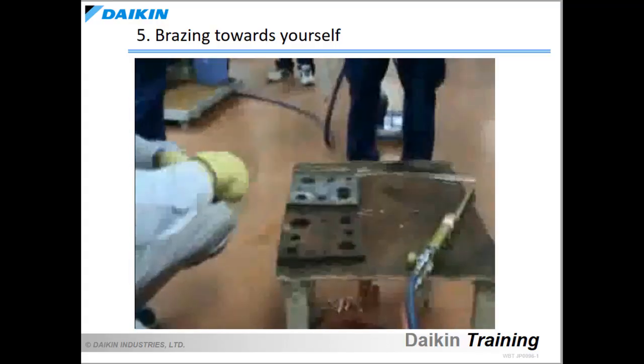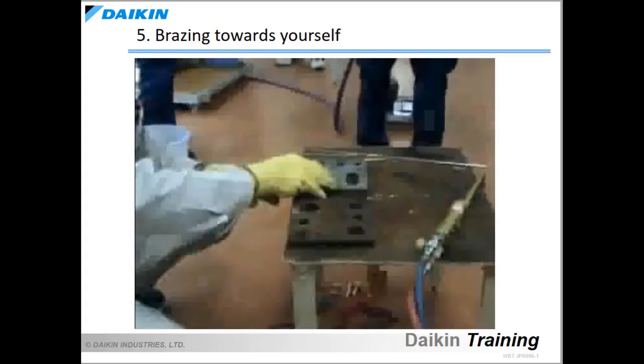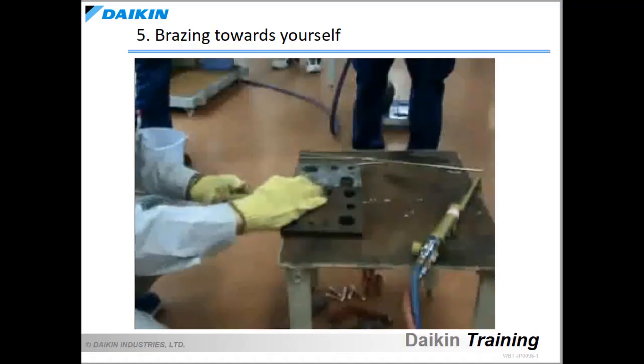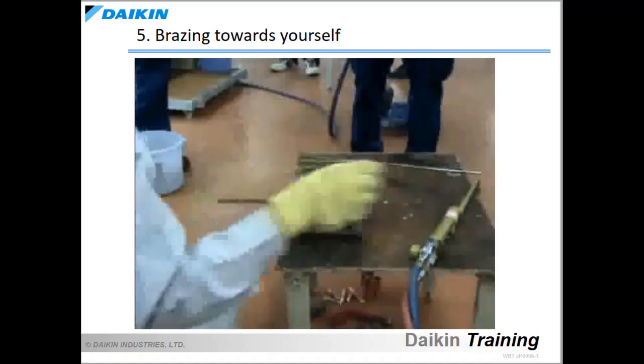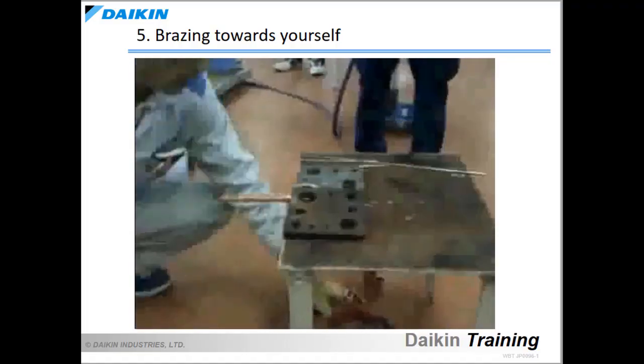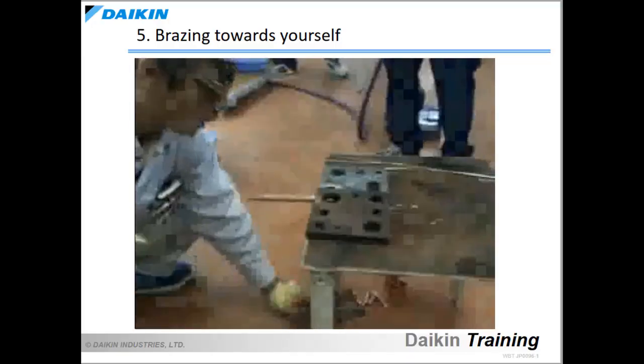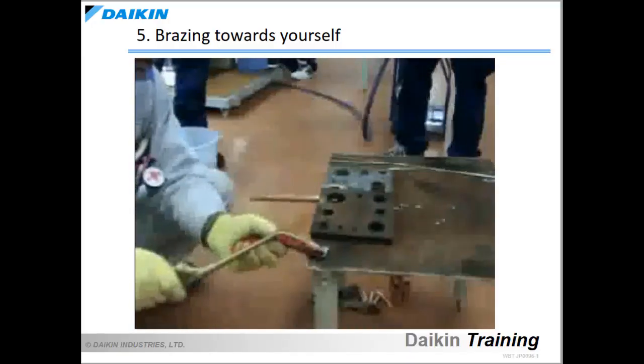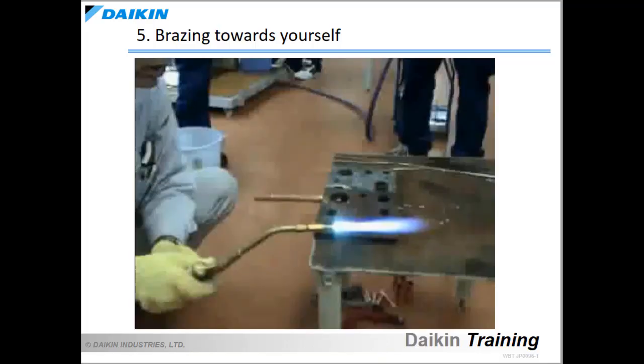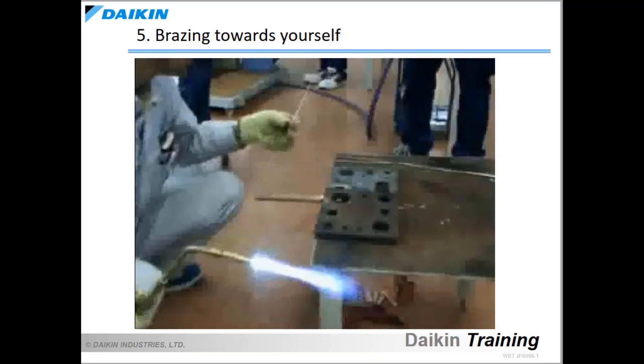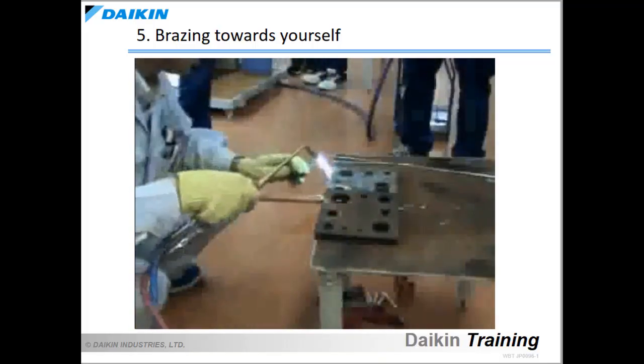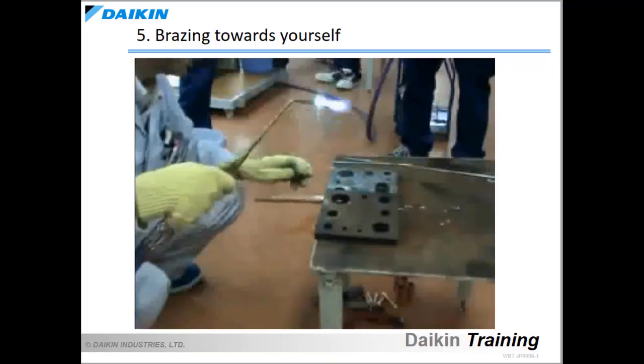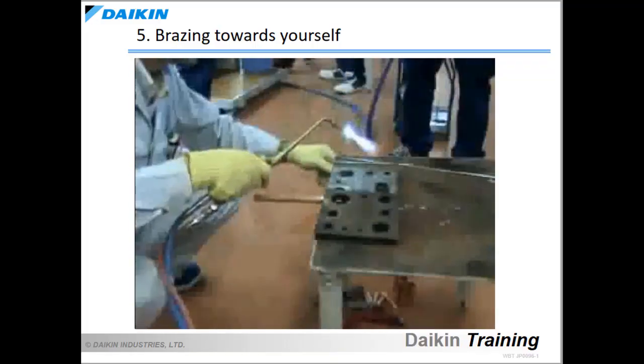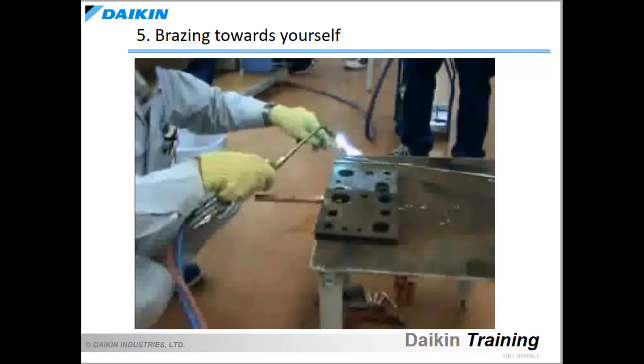Let's now review the brazing work towards yourself in the video. Light the torch and adjust the flame to the reducing flame. Bend the brazing filler metal rod at approximately 2 inches from the tip at a 90-degree angle. Heat the inner pipe first and then the outer pipe so that both pipes are heated evenly to the same temperature. Move the flame downward and distribute the brazing filler metal from the top to the bottom.